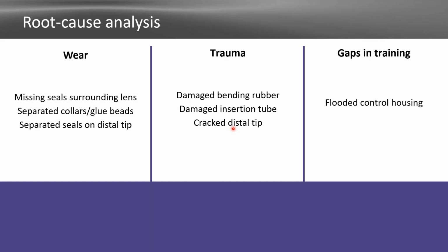I actually had one account where they were transporting the transducer on a system, and they had a semi-rigid, really thin wall piece of PVC attached to the side of the machine with bungee cords, and it was very creative, and they believed they were doing a great job in protecting the probe. The problem was that that PVC would run into doorways and things like that, and it would kink the probe. And once you kink those insertion tubes, that tube is damaged and it does have to be repaired. And then gaps in training, which would be the flooded control housing. If we have a flooded control housing, somebody has not been trained properly to care for these probes.